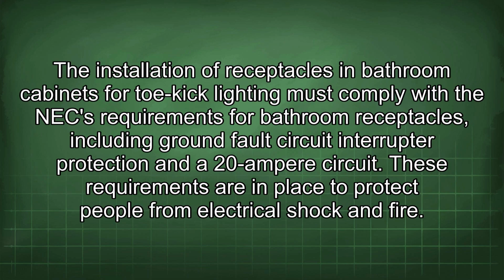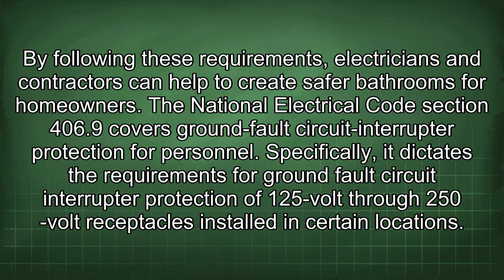The installation of receptacles in bathroom cabinets for toe kick lighting must comply with the NEC requirements for bathroom receptacles, including ground fault circuit interrupter protection and a 20 ampere circuit. These requirements are in place to protect people from electrical shock and fire. By following these requirements, electricians and contractors can help to create safer bathrooms for homeowners.